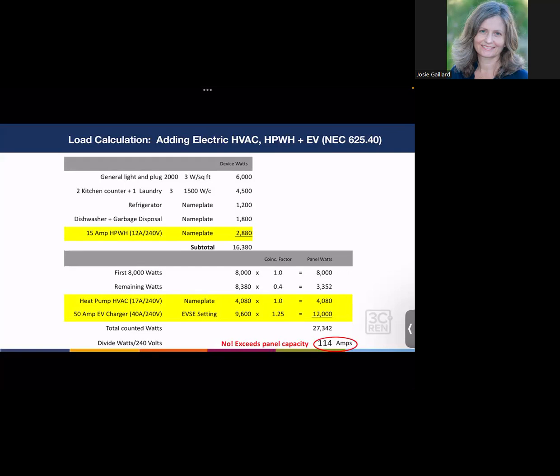Okay, now we get into some of the new devices, which are in yellow. So there we have the 15 amp heat pump water heater, which has a nameplate rating of 12 amps and 240 volts. You'll notice that we call it a 15 amp water heater, but the rating is actually 80% of how it's described. So 12 amps instead of 15 amps. So that's why it's important to look at the nameplates or get the data sheets if you don't have the appliance on hand. And we get a nameplate of 2,880. So we total those up and we get 16,380 device watts.